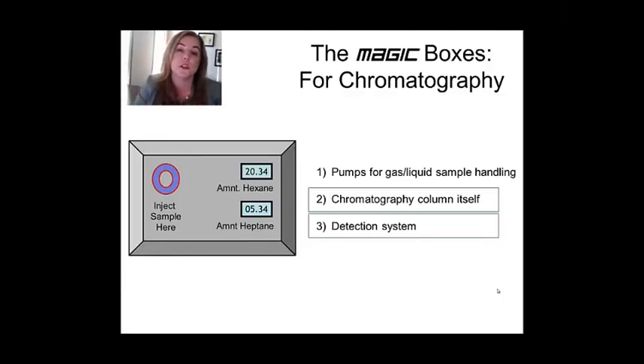You've got to be able to pump material into your system. So, chromatography instruments often have a lot of pumps. You're going to have to handle liquids or gases. You're going to have to modulate the flow. You're going to have to have a way to deal with the waste in both cases. Then you're going to have a column itself where all the separation takes place. You know, one's going to move faster than the other. If you have 50 components, you hope they all move at slightly different speeds. And then down at the end of the column, you're going to detect.